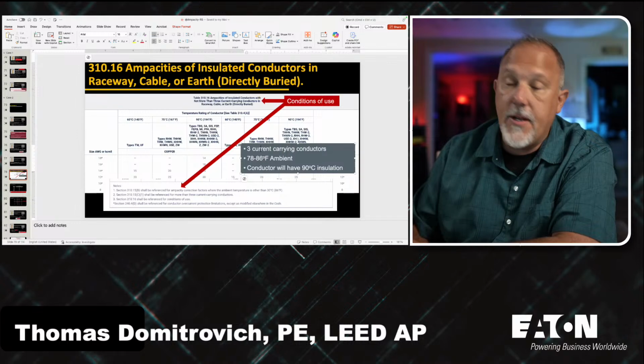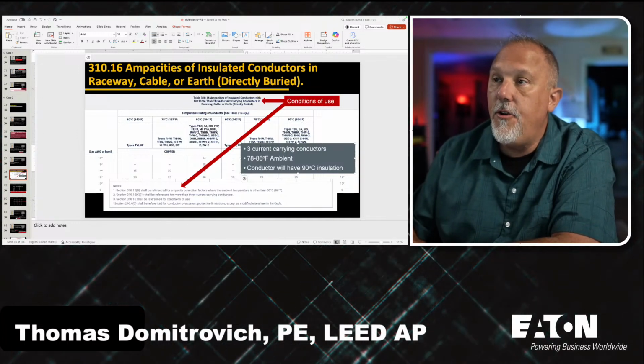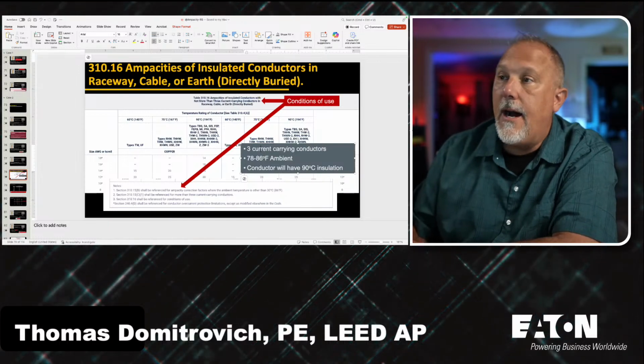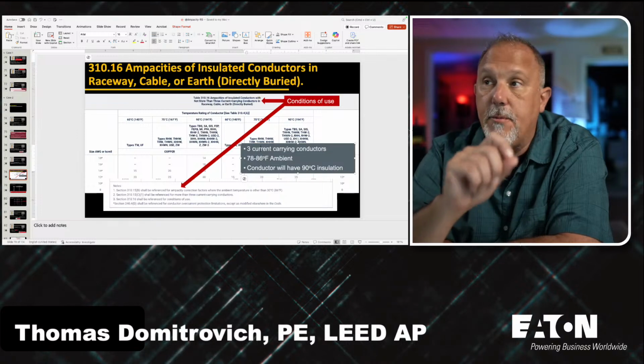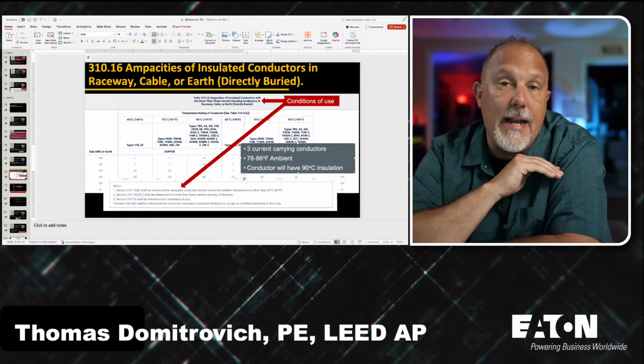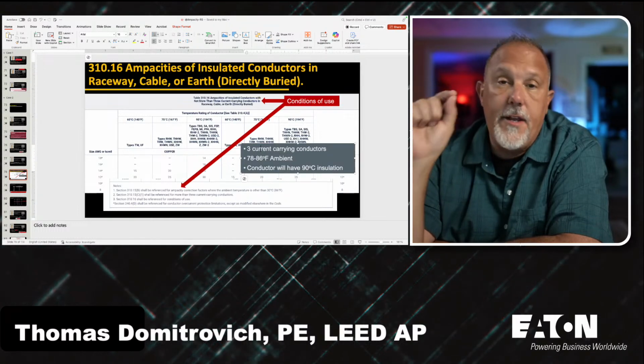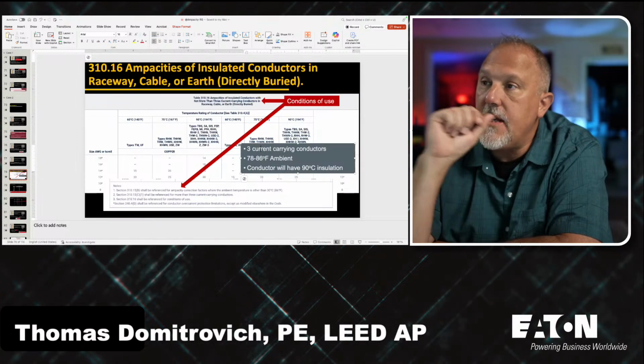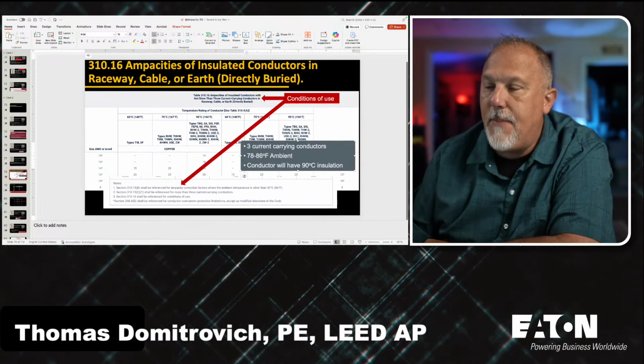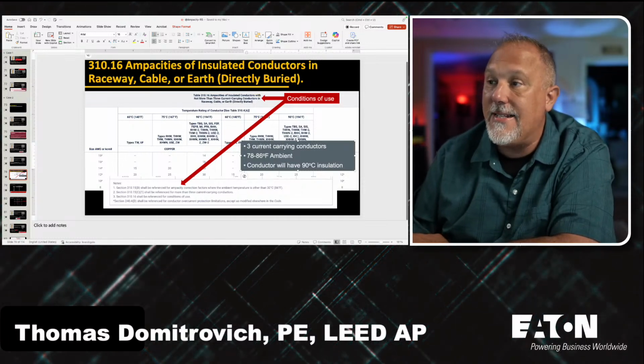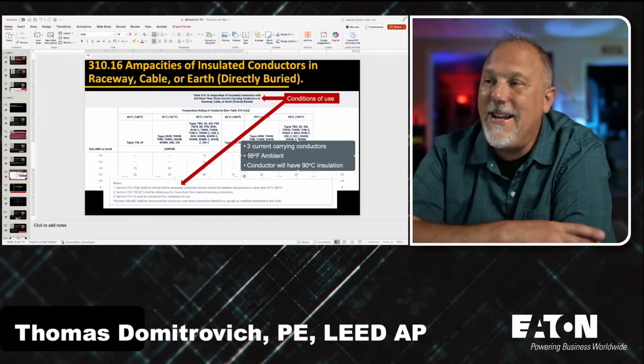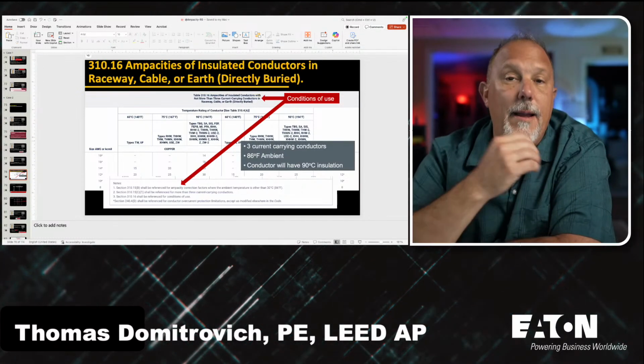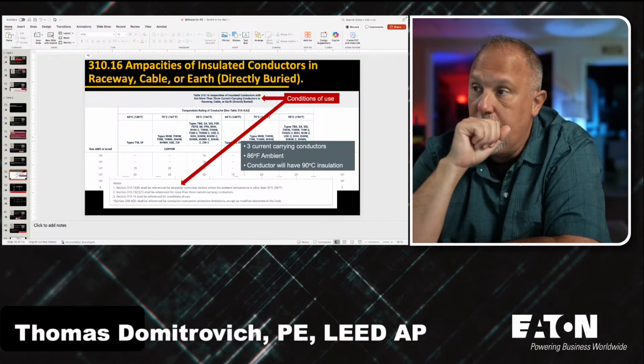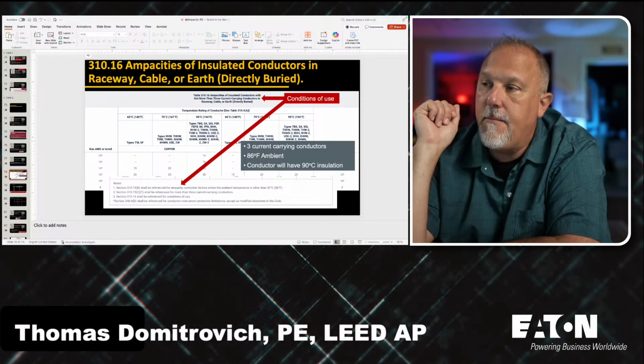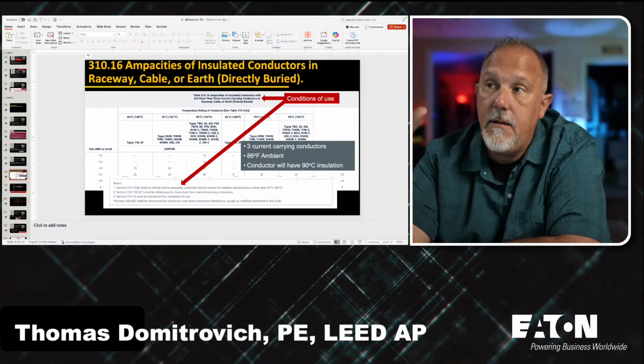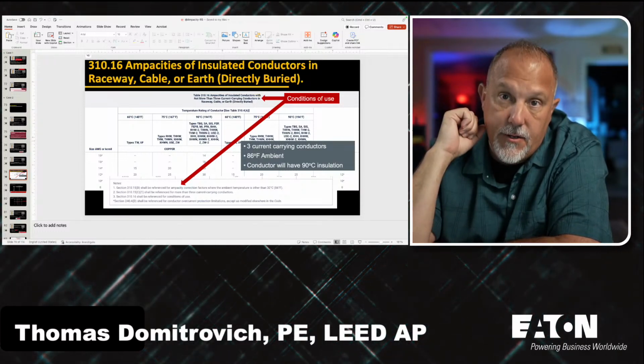All right, so I know I have 3 current carrying conductors. And what do I have here? Not more than 3 current carrying conductors. So I am meeting the conditions of use of table 310.16. I don't have to apply any adjustment or correction factors for the number of conductors in a raceway. The second one references the ampacity correction factors where the ambient temperature is other than 86. And look at that, I am at 86 degrees Fahrenheit ambient. So I'm wunderbar. Okay, I'm perfect. I'm at 86 degrees Fahrenheit, and my conductors have a 90 degree insulation. So I am within the conditions of use of table 310.16.